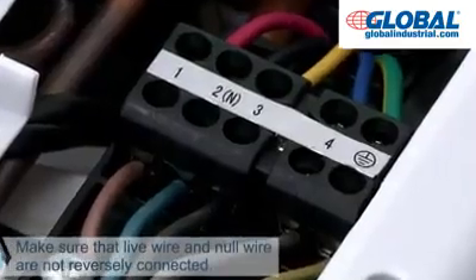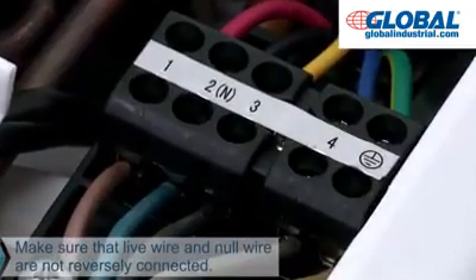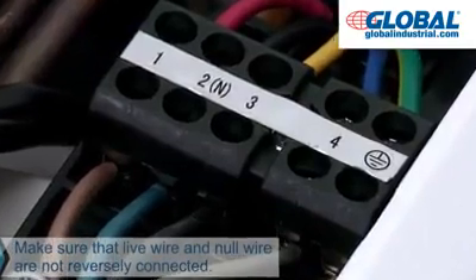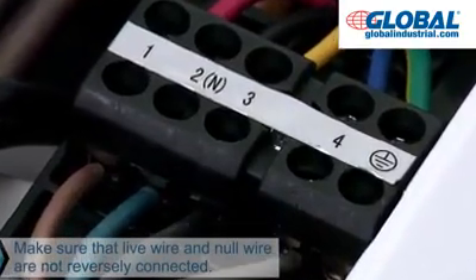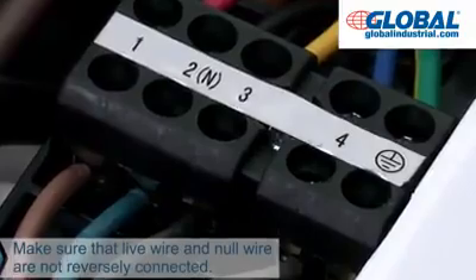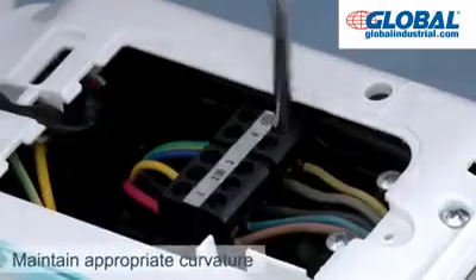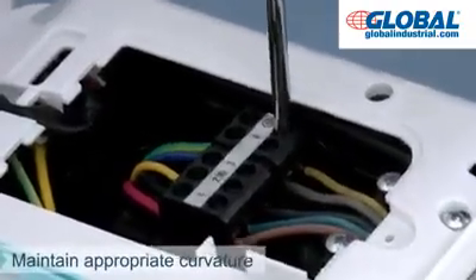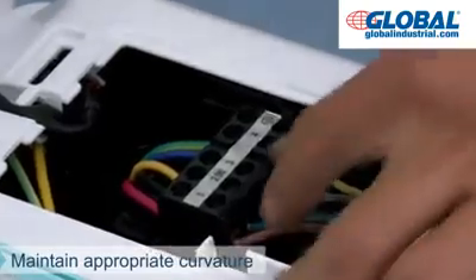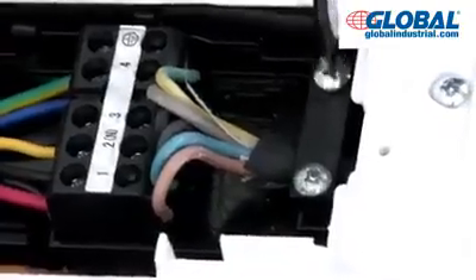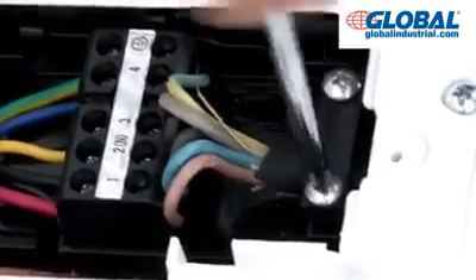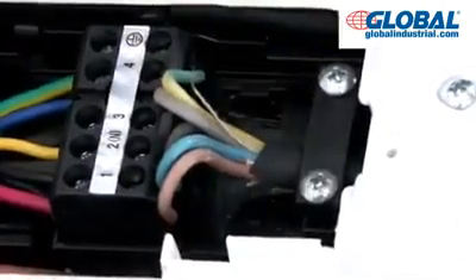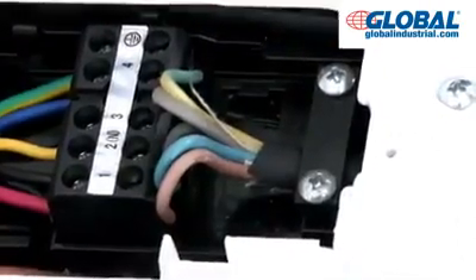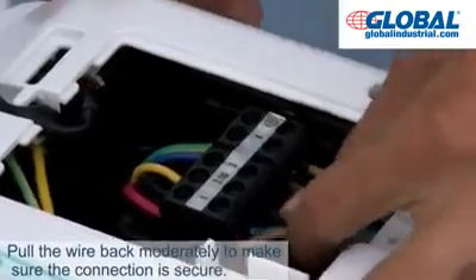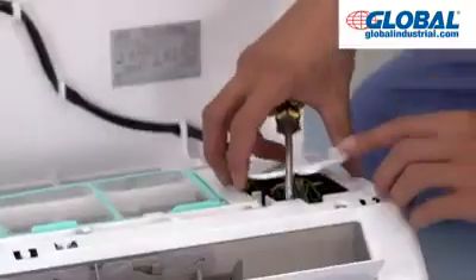Special attention should be paid if the live wire and null wire are incorrectly connected. The air conditioner may not work regularly as a result of malfunction. Maintain appropriate curvature to avoid the loosening of the wire terminal under stress. Compress the connecting wire with the press wire card and get the press wire card fixed. Pull the wire back moderately to make sure the connection is secure. Mount the cover of the electric control box.